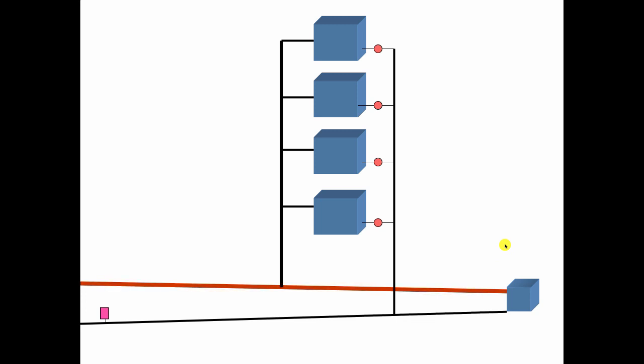Now this is the way it's supposed to work. Steam goes down the end, the F&T trap stops it, rises up here, passes through, stops at the traps, air gets vented out of the main vent over here. That's the way it's supposed to be.